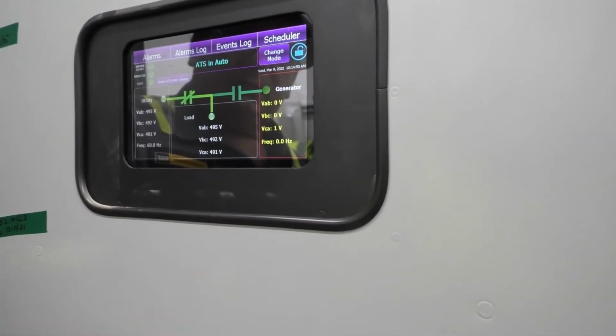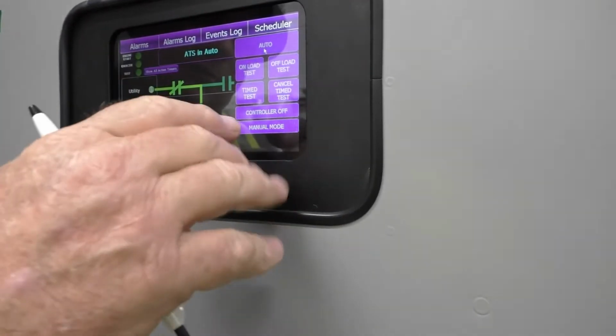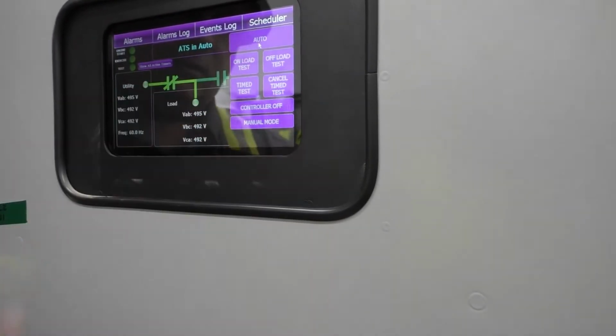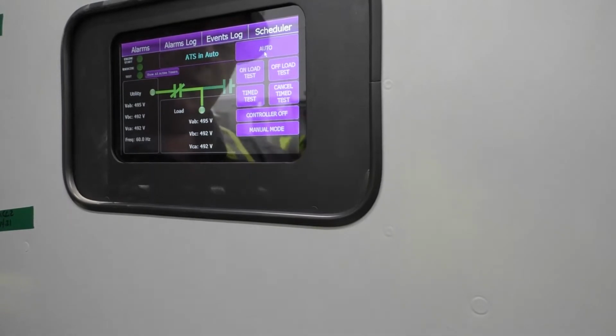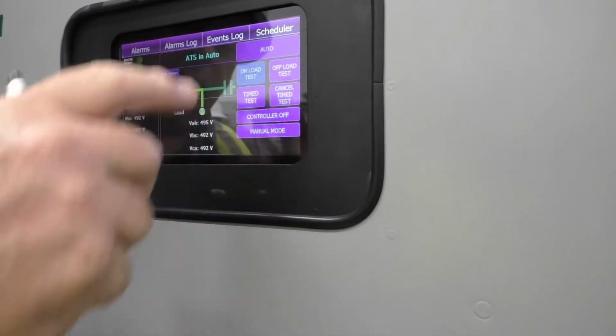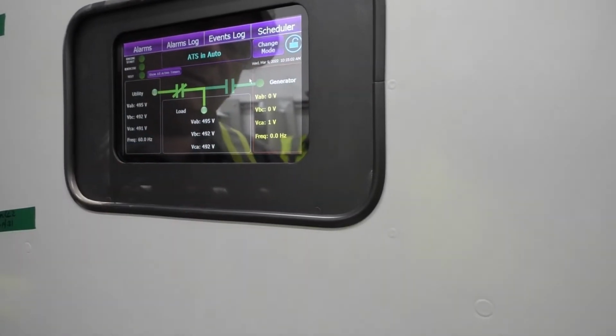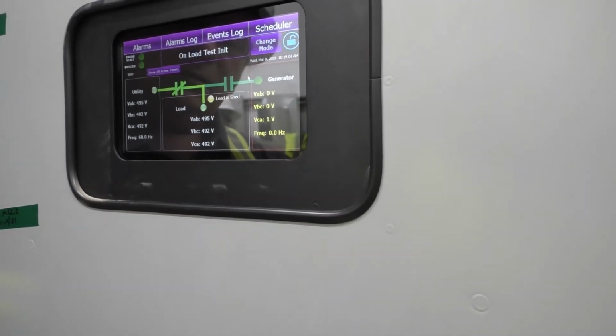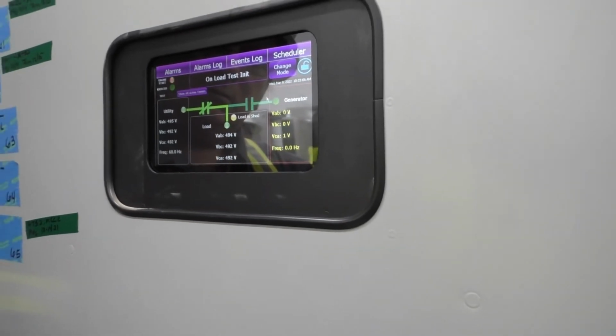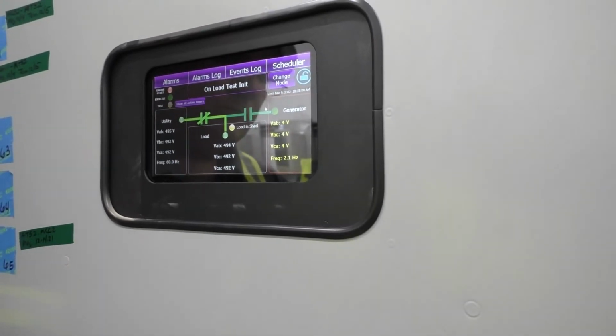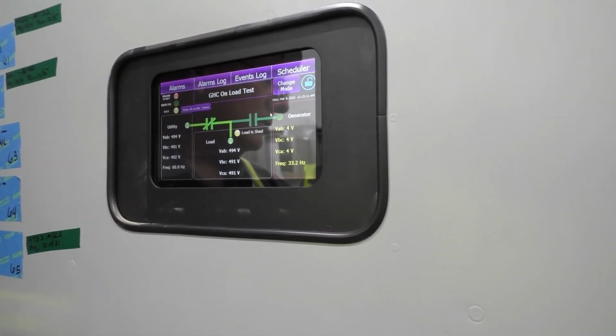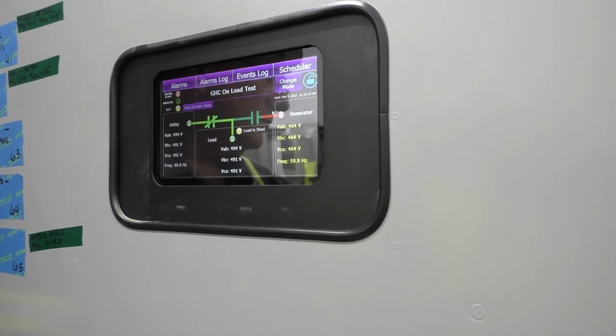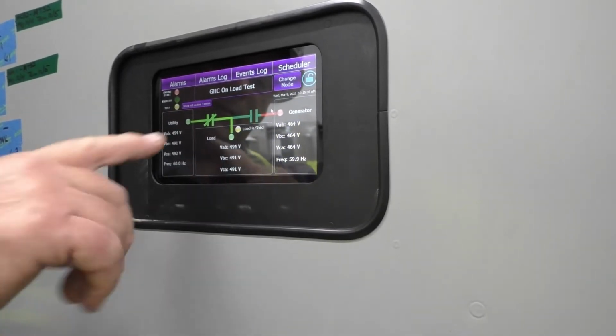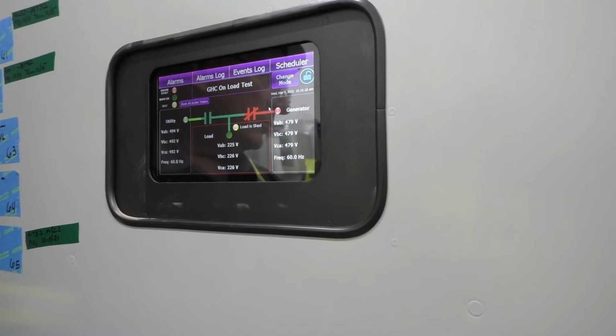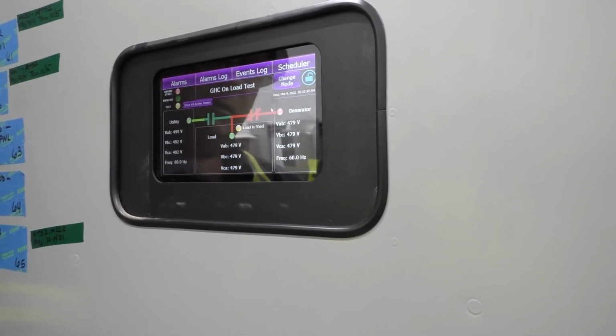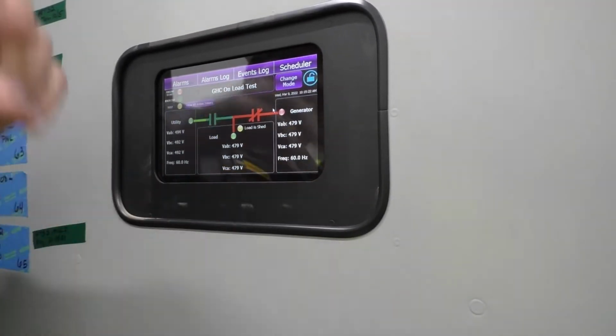If we want to run a test, the easiest way is to go to the change mode, do an on-load test or an off-load test. Off-load means it'll just run the generator, it won't transfer. On-load means it's going to transfer, so it's a few second delay. Nobody's going to get hurt out there working. Now we're open, now we're closed. Yeah. So we're on generator.